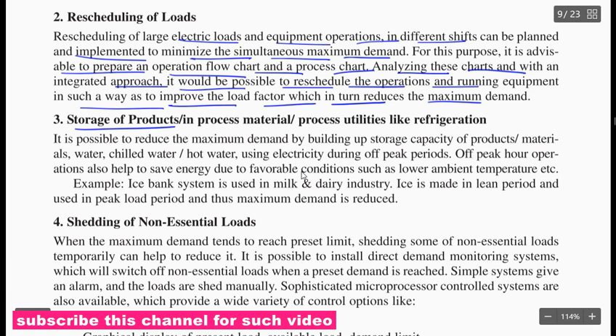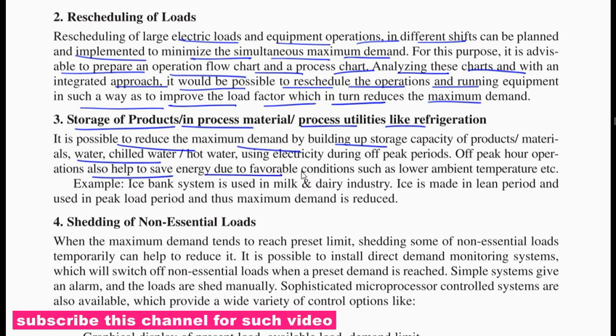Storage of product, in-process material, and process utilities like refrigeration. It is possible to reduce the maximum demand by building up storage capacity of product, material, and water, chilled water, hot water, and using electricity during the off-peak demand. Off-peak hour operation also helps to save energy due to favorable conditions such as lower ambient temperature.